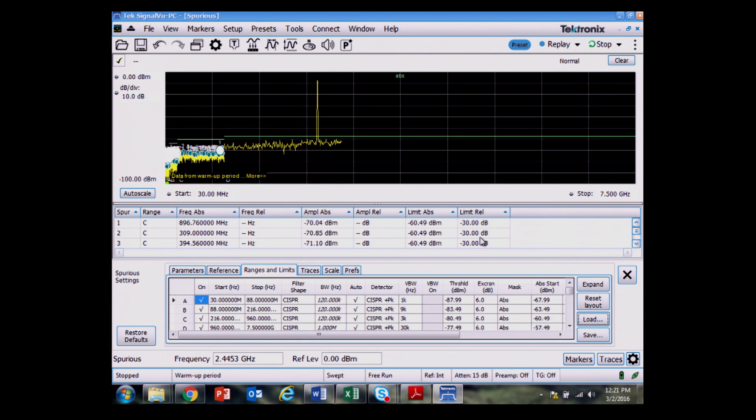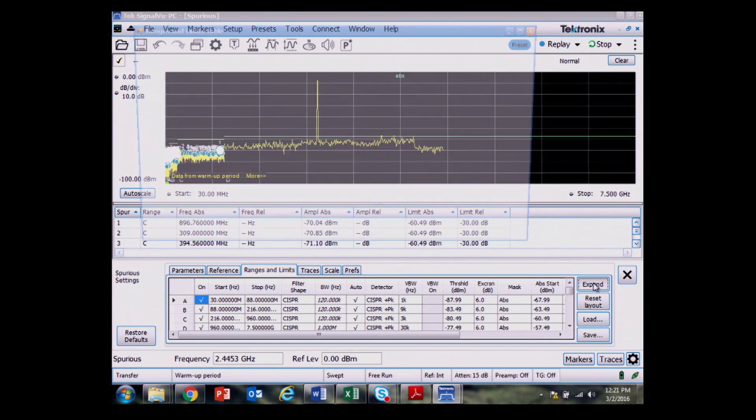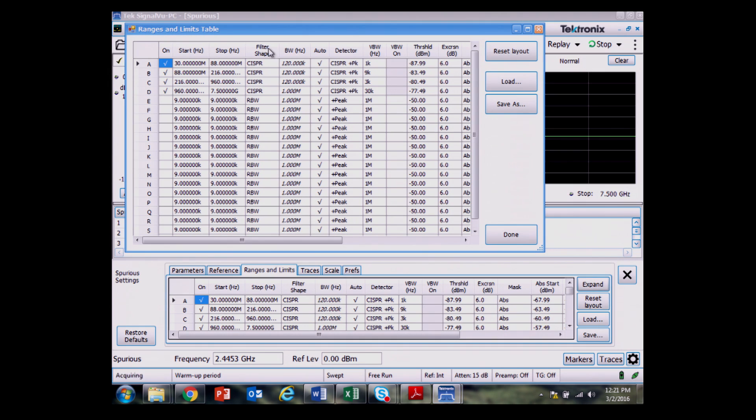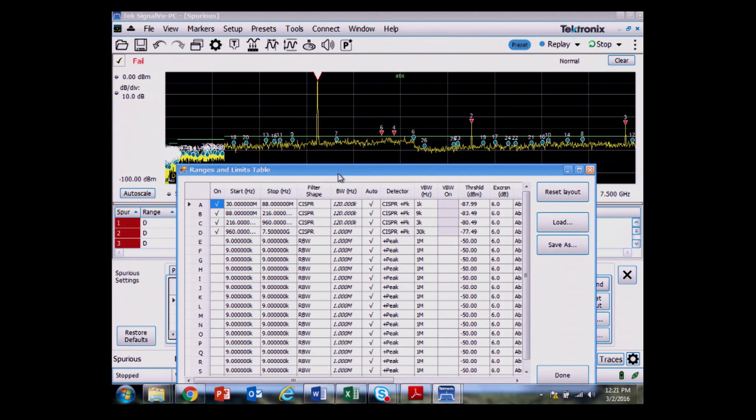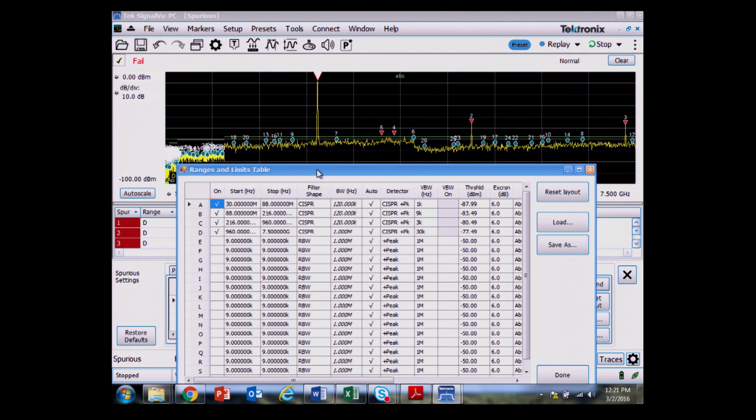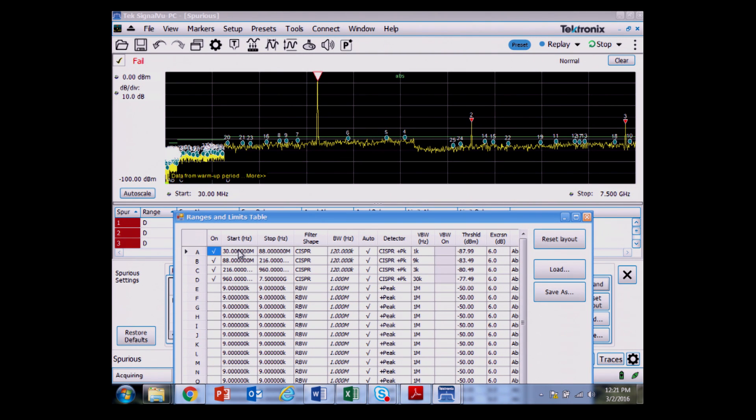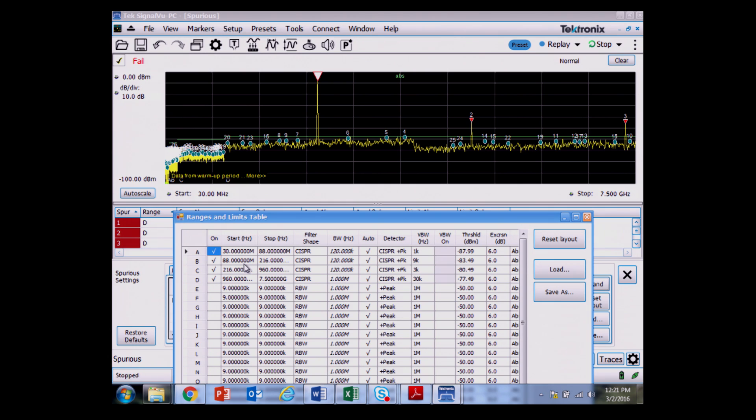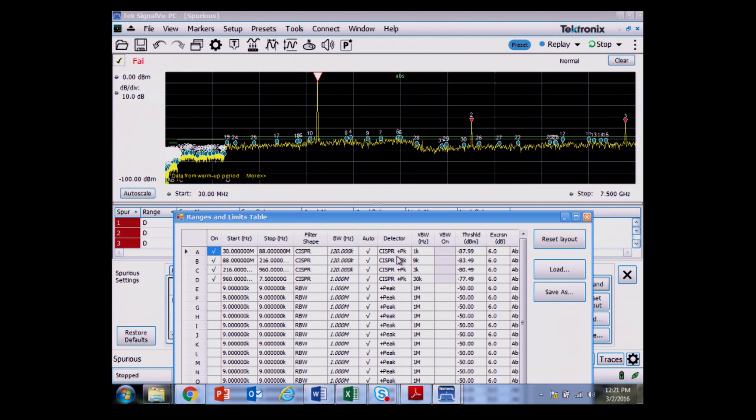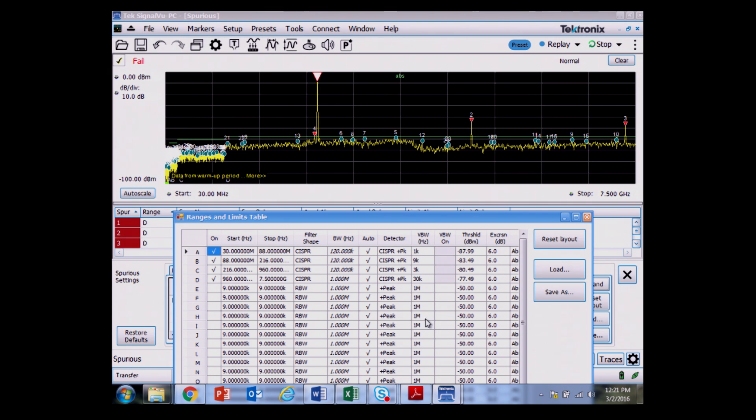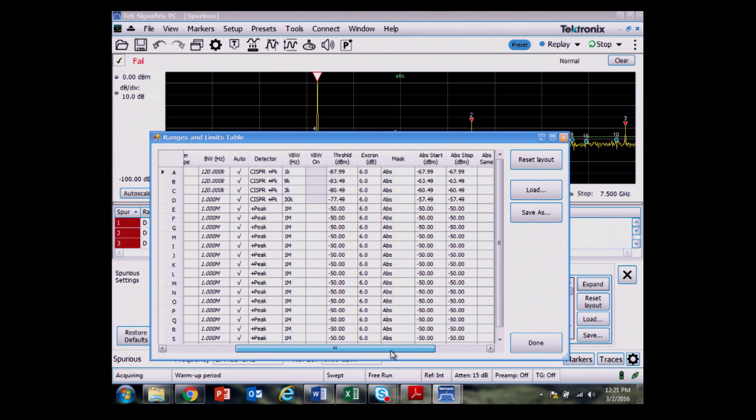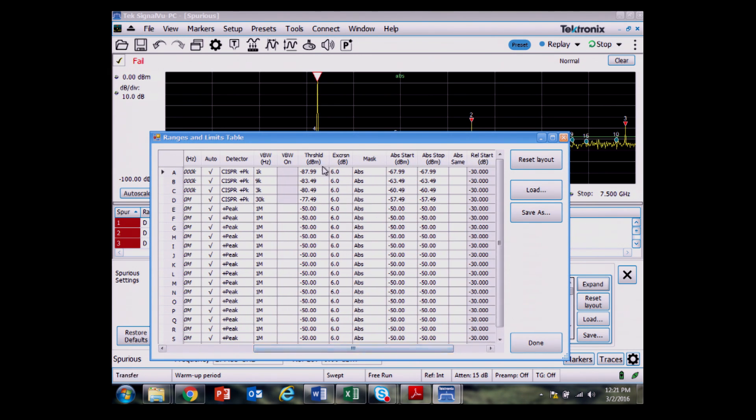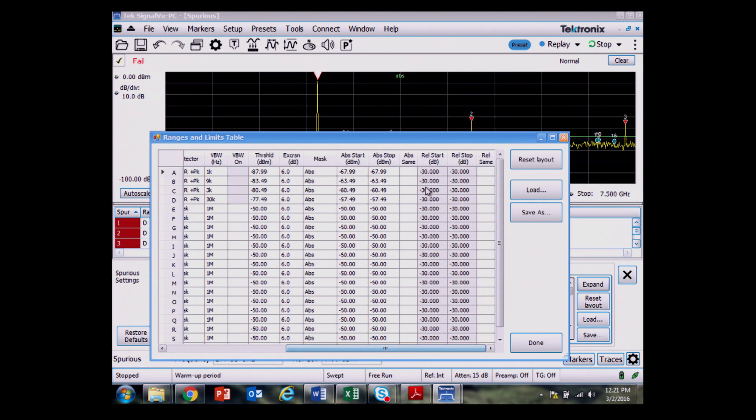What's already been defined here in the table are four different zones. I can move this out of the way so we can still see the measurement. I have four different zones per the FCC part 15 test. The start and stop frequencies, the CISPR shape with a plus peak detector, video bandwidth, and then some different thresholds that define first a spur and then define the limit lines for the test.